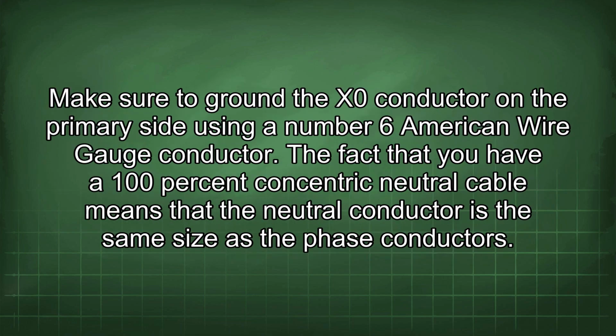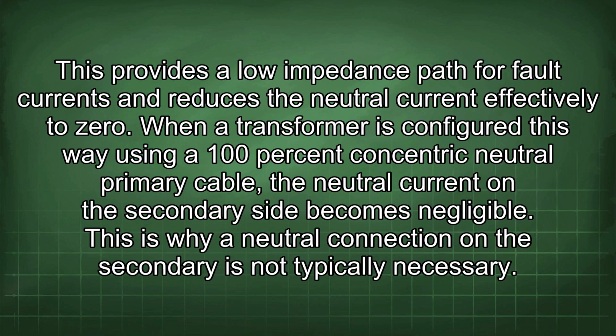Make sure to ground the X0 conductor on the primary side using a number 6 American wire gauge conductor. The fact that you have a 100% concentric neutral cable means that the neutral conductor is the same size as the phase conductors. This provides a low impedance path for fault currents and reduces the neutral current effectively to zero. When a transformer is configured this way using a 100% concentric neutral primary cable, the neutral current on the secondary side becomes negligible. This is why a neutral connection on the secondary is not typically necessary.